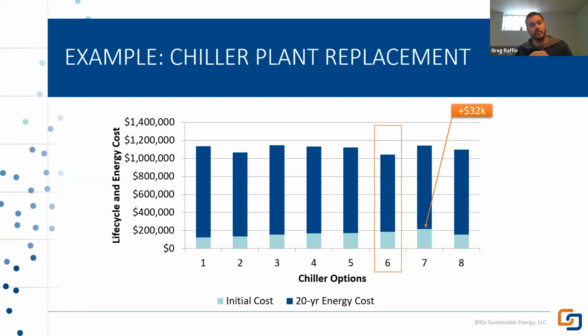But because of how the performance data fell out, and how this building's load profile actually uses energy, that 'more efficient' expensive chiller would have cost about $100,000 more over its life cycle. Chiller number 6 was less expensive and had a much better life cycle cost. They could have also gone with the cheapest chiller and saved $60,000 up front, but that, oddly enough, would also have cost about $100,000 more over the life cycle.